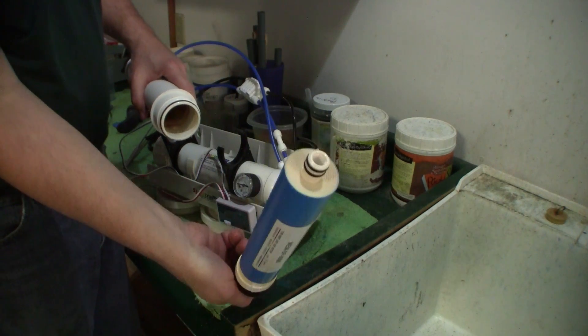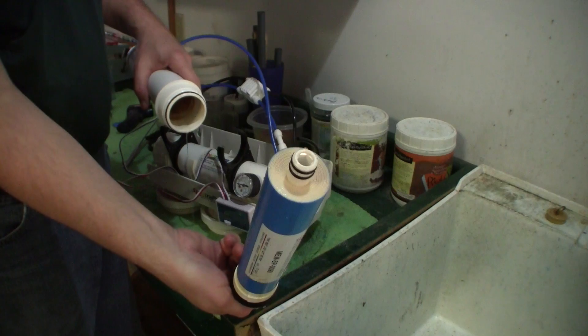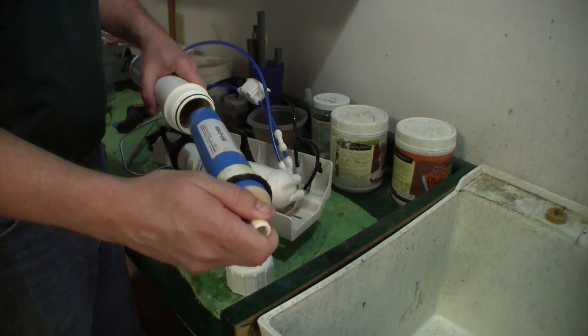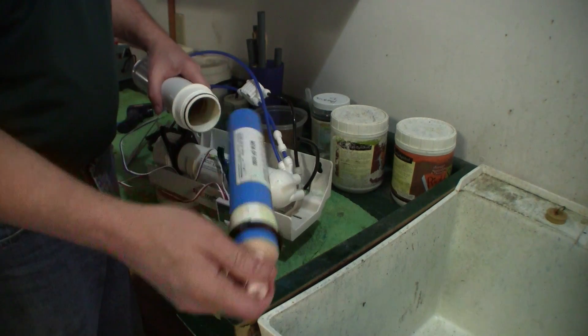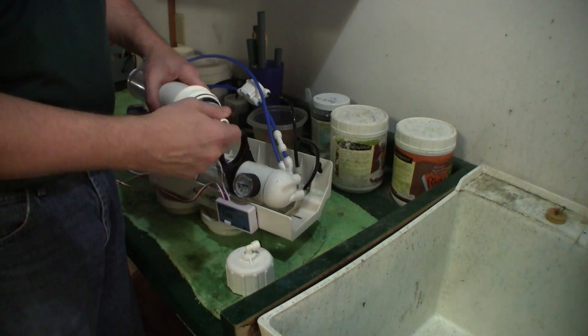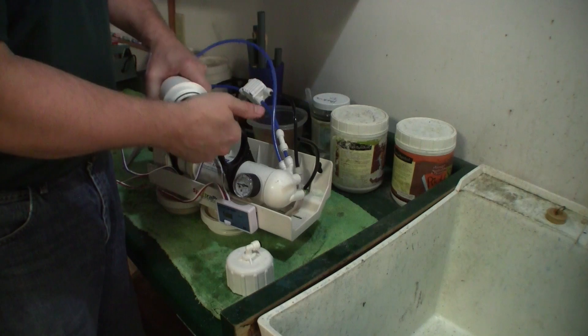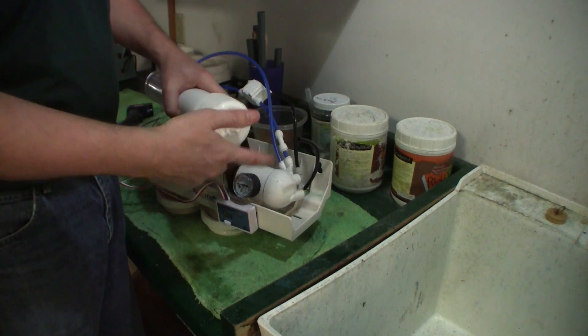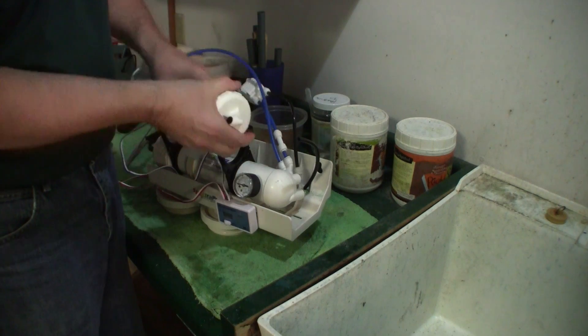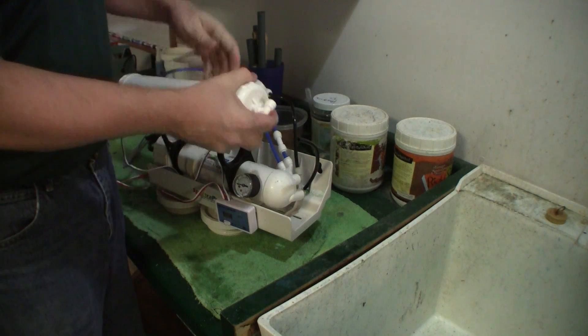One end of the membrane has got these little gaskets on it. That is the end that goes all the way into the back end of the chamber. So you take your new membrane, you shove it in there, make sure it's seated. And screw the cap back on.